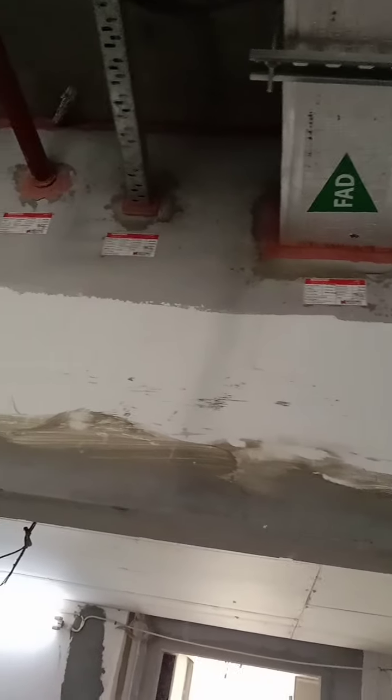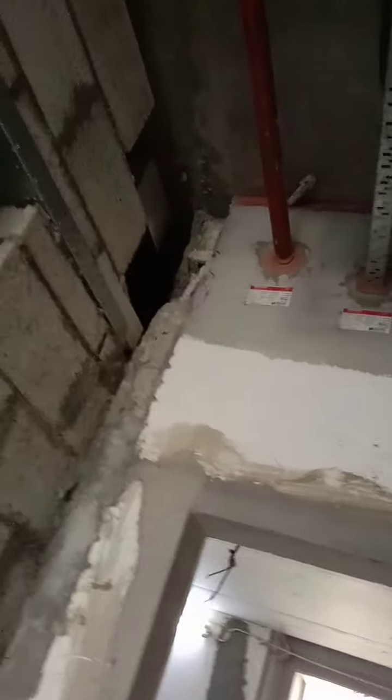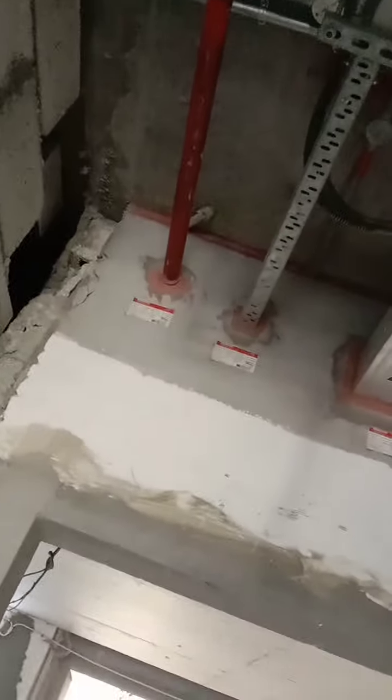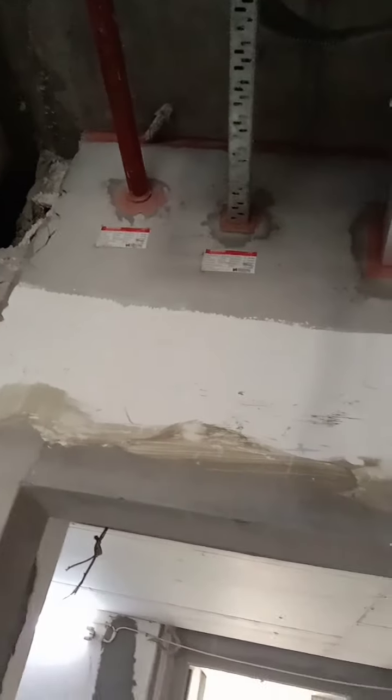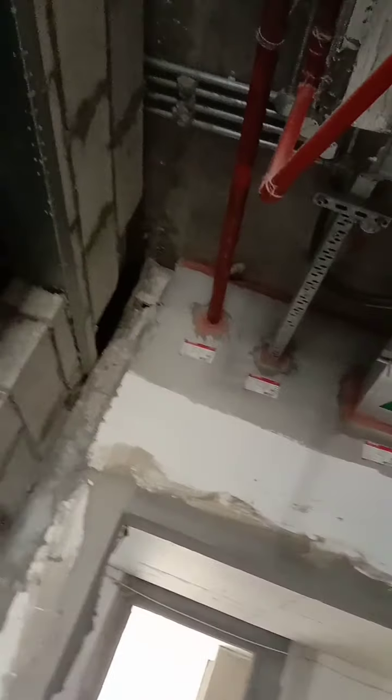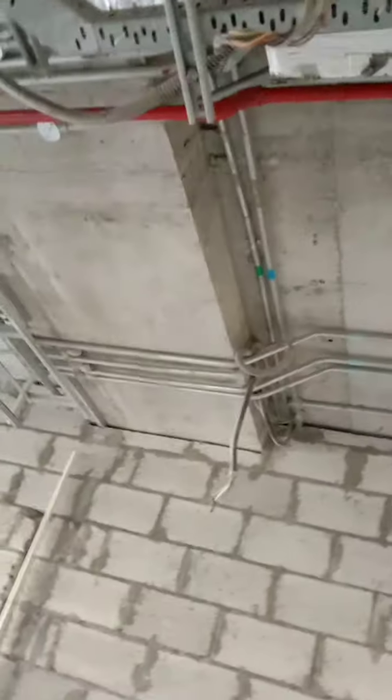For a non-fire rated wall, we just have to put in PU foam or the non-fire rated sealant. So for all the different penetrations, we have to ensure that we have our fire sealants or the sealants provided, as well as putting a sticker. Then this inspection also will be raised before we sign off for that particular service, which is very important. As you can see, also the GI conduit penetration, we've done the fire stopper, which is very important. So everything has been done.